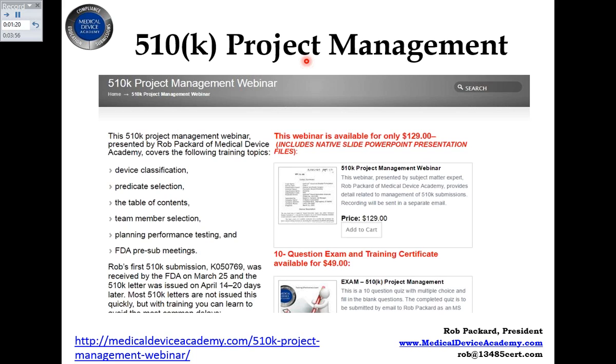You do your performance testing to show safety and efficacy, and you may even have a pre-sub meeting. In this webinar, you're going to get a lot of information about how to do those early things at the beginning of a 510K project: classification, predicate selection, putting together a team, and planning your performance testing, whether it's benchtop or animal testing or even a clinical study.